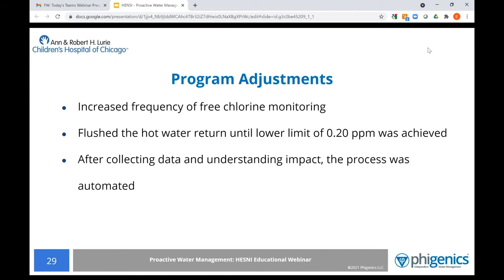We had a breakthrough in the spring of 2020 when, in consultation with Phigenics, we decided to flush the domestic hot water return. This is at the point where it connects to the domestic water heaters. Once we started flushing, we saw a large increase in the free chlorine levels throughout the building hot water system. This improvement led to reduced positive cultures for both Legionella and THAB, and a subsequent increase in water quality for both the hot and the cold water at the fixtures.